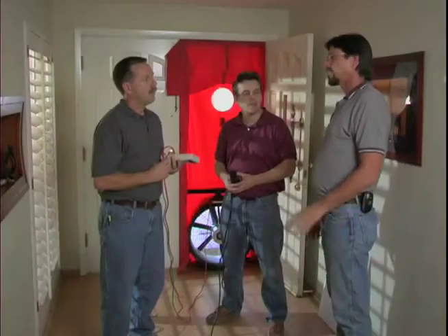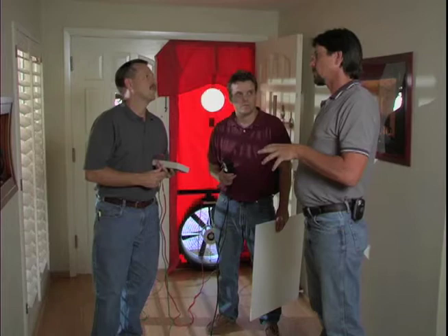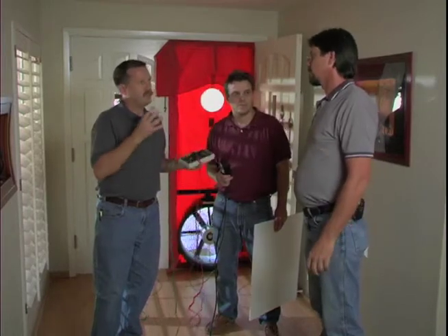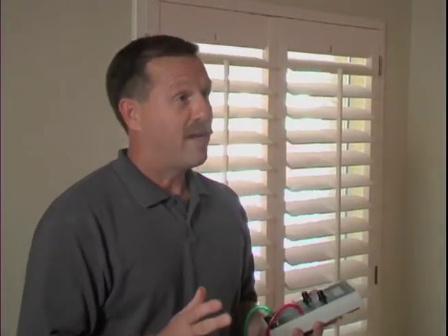the house. One thing that we can do is we can tape off all the supply and return grills and rerun this test and find out exactly how much is duct leakage and how much is infiltration leakage. So we'd find that by subtracting that number from the 4,800? Correct.